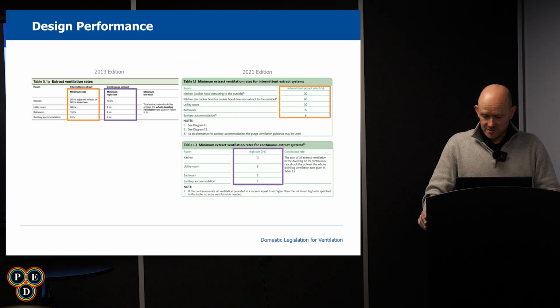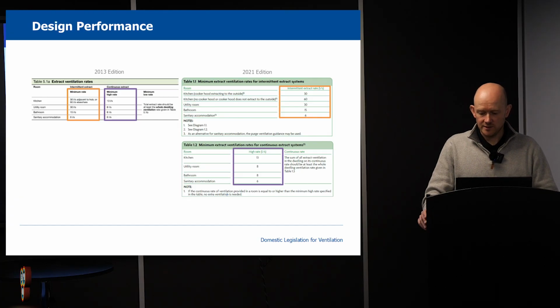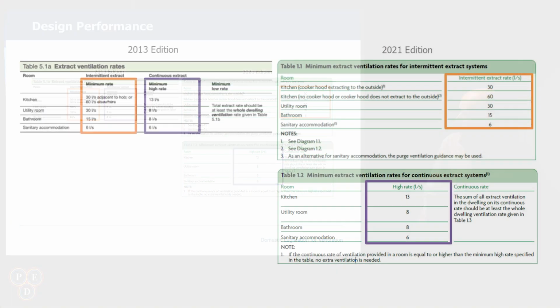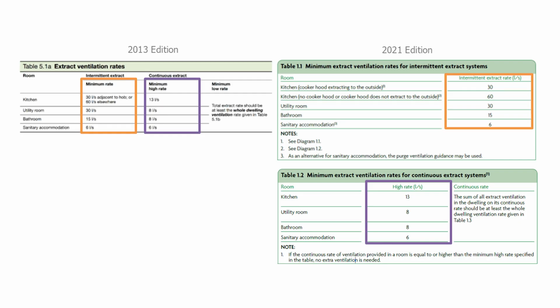The minimum intermittent and high extract rates between the 2013 and 2021 editions remain unchanged and are presented within table 1.1 and 1.2. For intermittent extract systems, there are 60 litres or 30 litres for a kitchen, 30 litres for a utility, 15 litres for a bathroom and 6 litres for a toilet. So if the cooker hood in that property is going out to atmosphere, it can be 30 litre. If they can't get it out to atmosphere and it's a recirculator, you need to put a fan in that is 60 litre to comply.